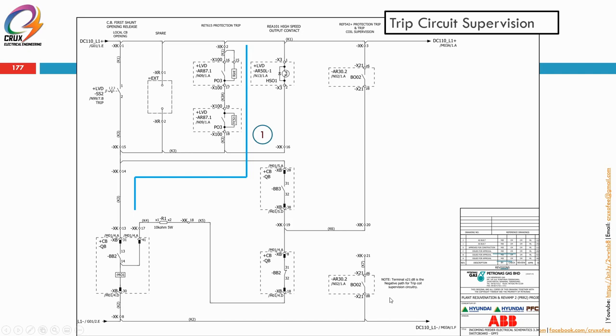Okay, this is a sample from an ABB drawing, which is showing a tripping circuit as well as the trip circuit supervision. Okay. So now let's assume that the breaker is in the open condition. Let's see whether the trip circuit supervision is monitoring the trip coil. So here is our trip coil MO1. Under the breaker open condition, the only way for the supply to be true is through this, but BO02 is normally open. So it's not monitoring. So this circuit is not monitoring when the breaker is in open condition.